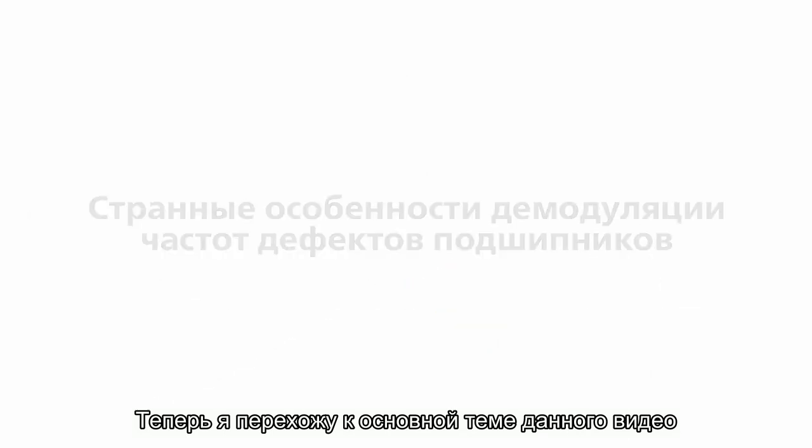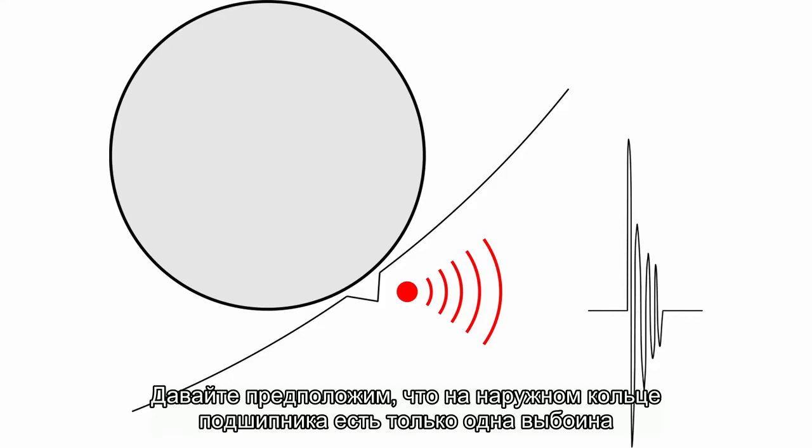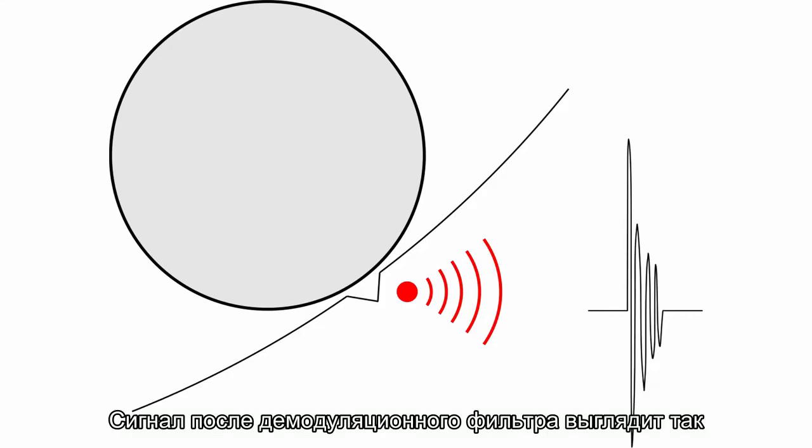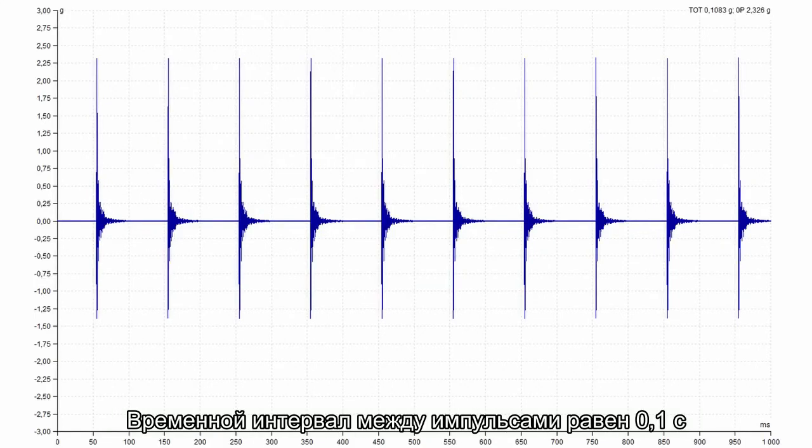Now I am starting to talk about the main subject of this video. Let's suppose the bearing with just one crack on the outer race. The signal after demodulation filtering looks like this. The time interval between shocks is 0.1 second. And it exactly corresponds to fault frequency, which is 10 Hz.